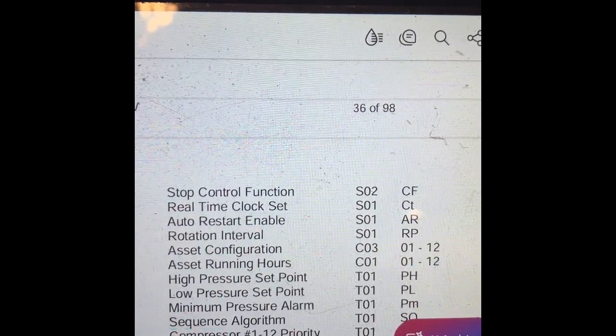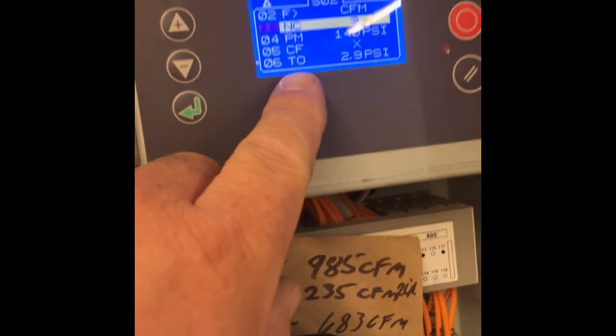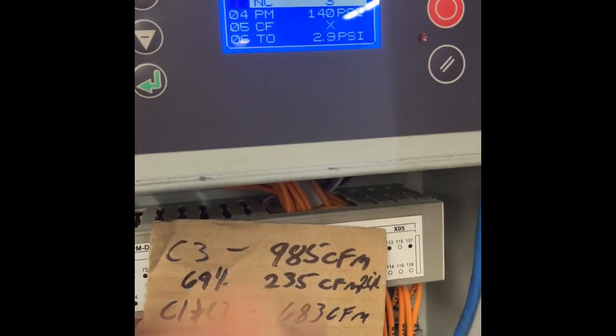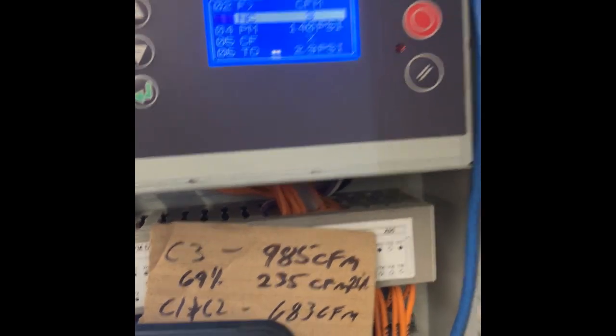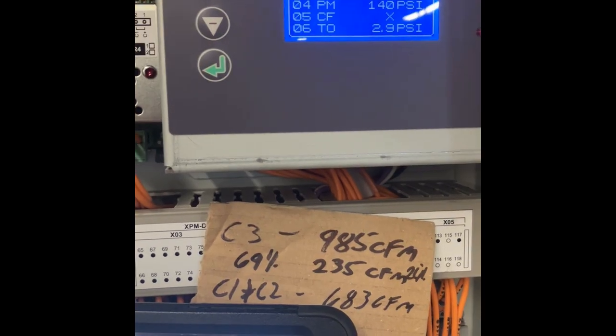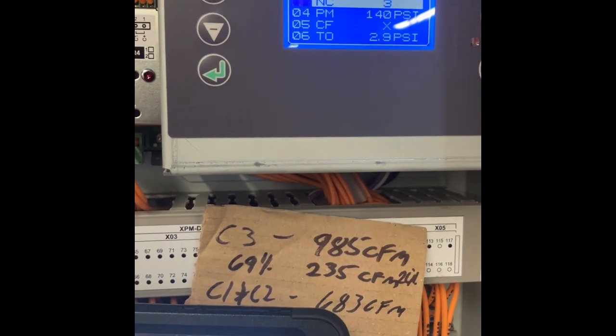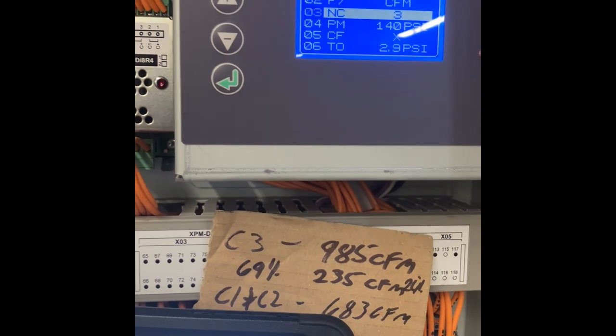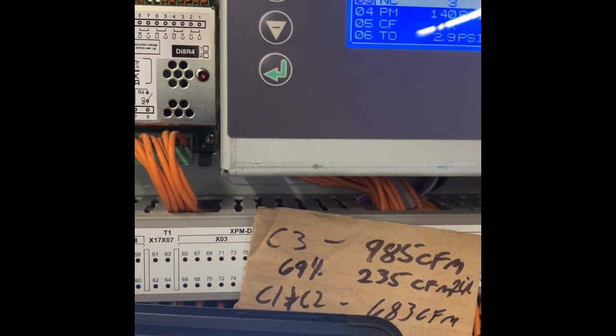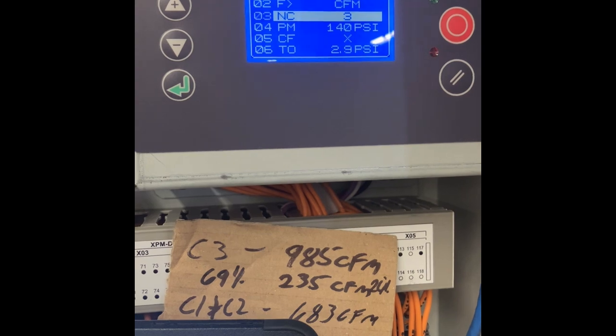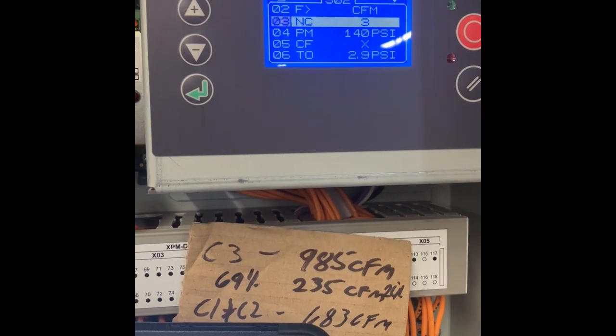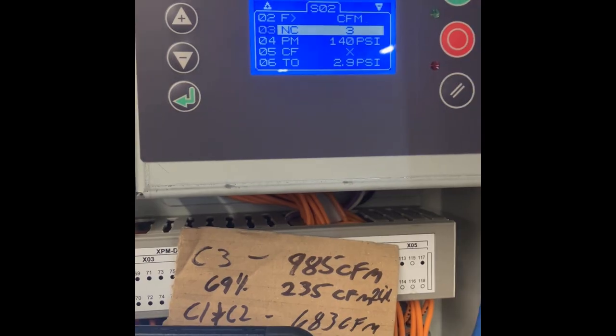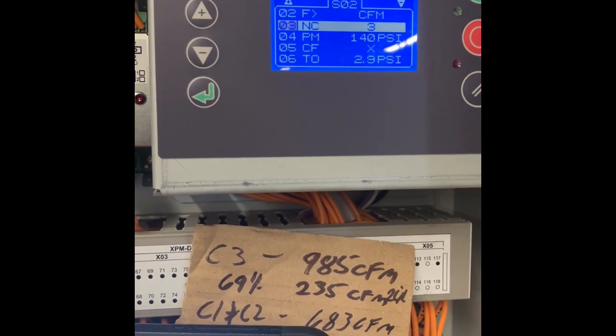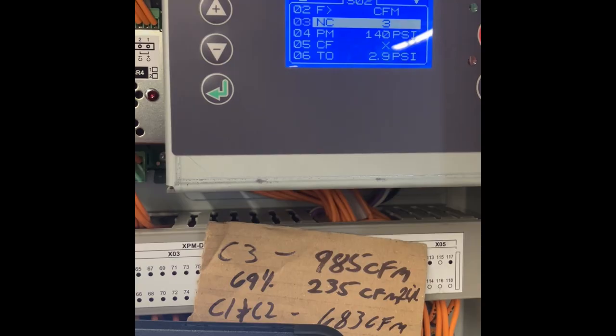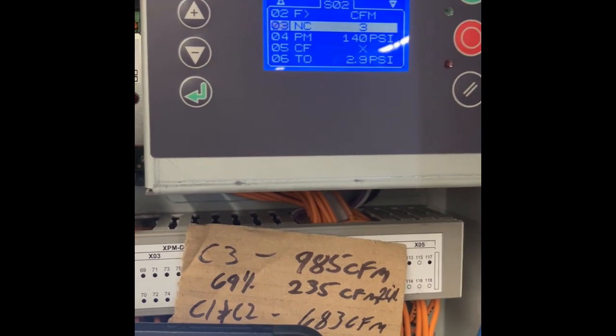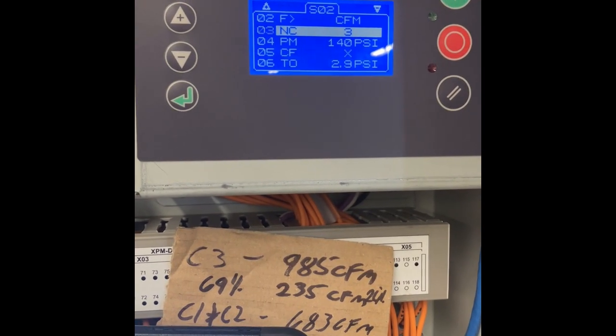all right, so whoops, CF, which is control stop function, you either get a check mark or an X. If you set it to an X, what that means is when you command the central controller off, it is going to unload the compressors and hold them in standby until you command the central controller back on. If that is set to a check mark, then what it does is when you turn the central controller off, it just returns the compressors to local control and lets them run as they may. It's going to be up to you and your customer which function works better for you.